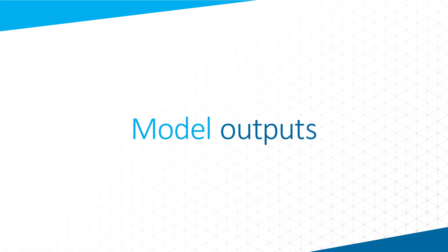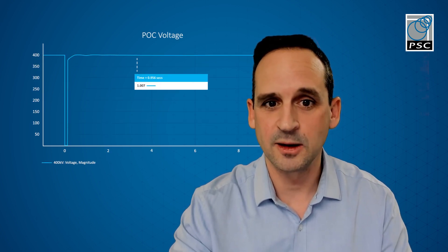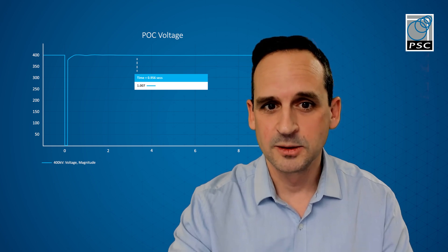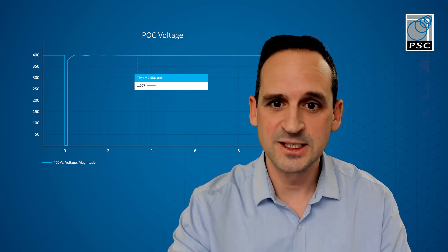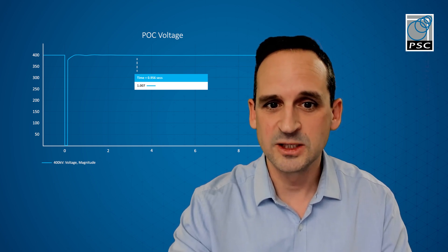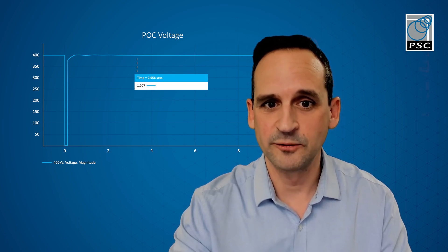Within DigSILENT, we've prepared graphs to see the output of the study. The main three things that we're looking for from the results are, primarily, does the generator remain connected? Does the active power recover to at least 90% of the pre-fault level within 500 milliseconds? And is reactive power injected during the fault?